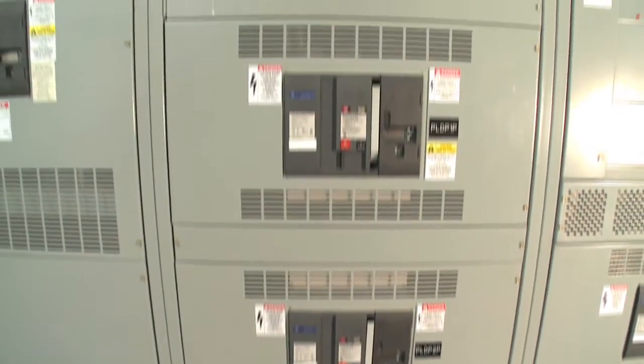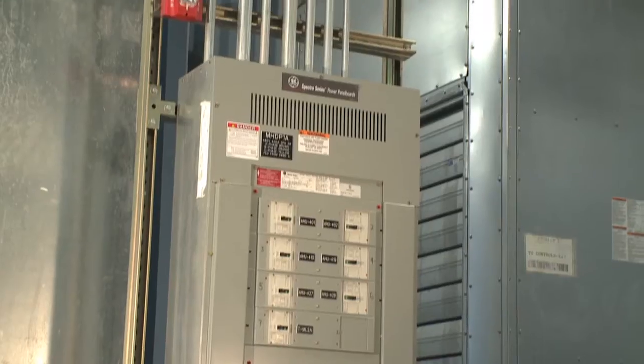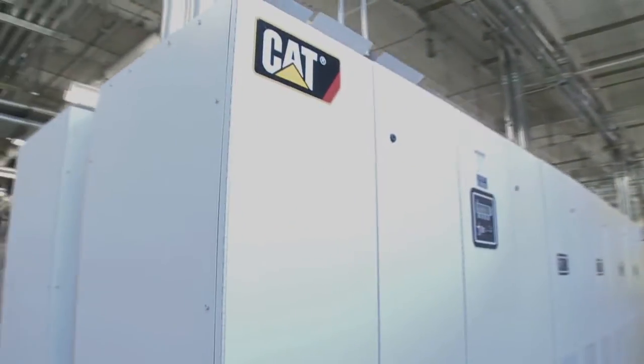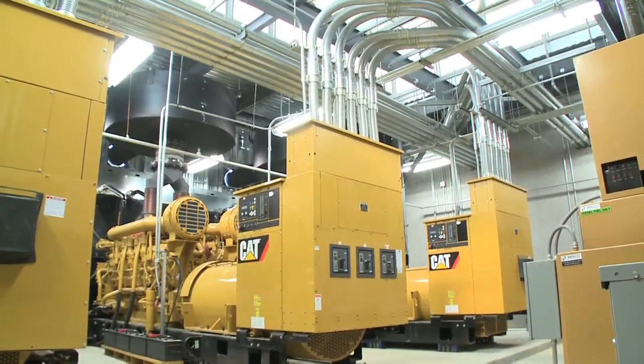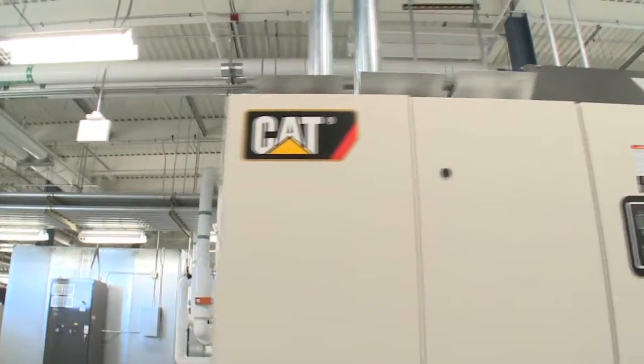In this design, one set of feeds extends up into the data center area to serve load requirements at the south end of the building, and a second set of conduit extends up into the mezzanine floor to be distributed to the load at the north end of the building. We use flywheel UPS systems that easily carry the required load in the event of a utility failure before transfer to the diesel generators. Not only can flywheel systems be more efficient than batteries, the advantages include the ability to house the flywheels in a warm ambient, which eliminates the cost to construct a special environment and also requires less physical space than a battery-based solution.